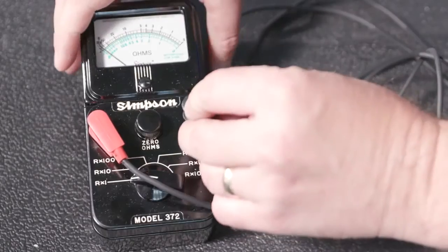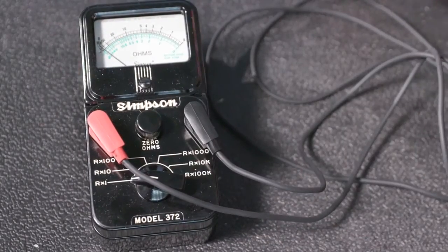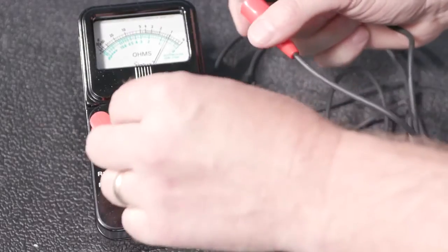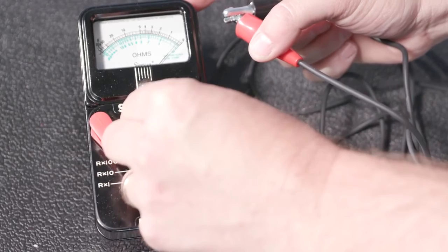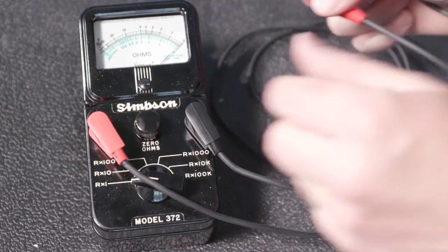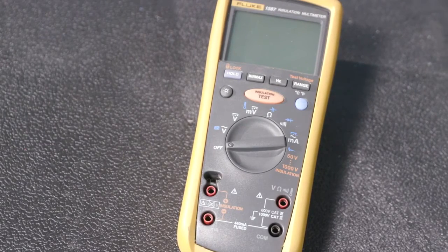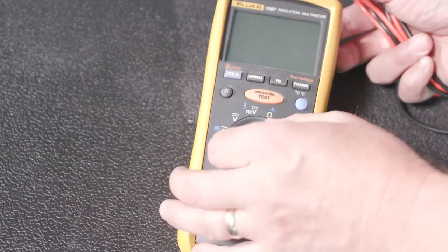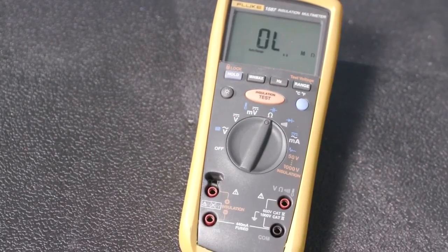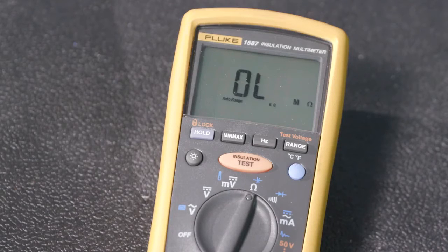Analog ohm meters, such as the Simpson 372, have an adjustable scale which must be set prior to taking the measurement. In addition, they may contain a dial to zero out the meter. Digital meters, such as the Fluke 1587, have auto-ranging features. Therefore, there is no need to manually adjust the scale prior to the measurement. The Fluke 1587 does not allow the meter to be zeroed out.